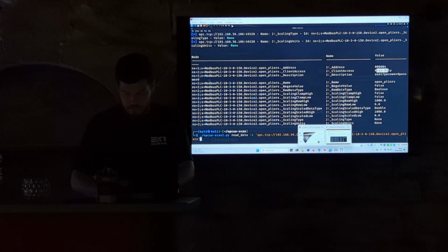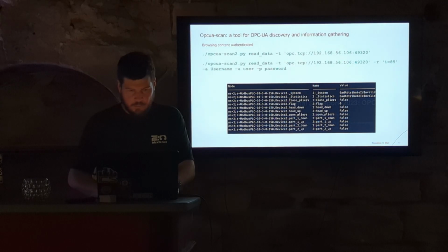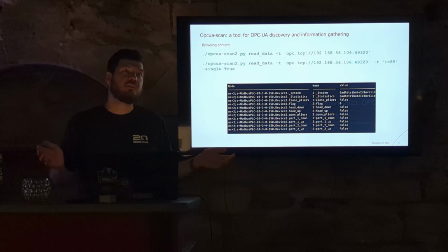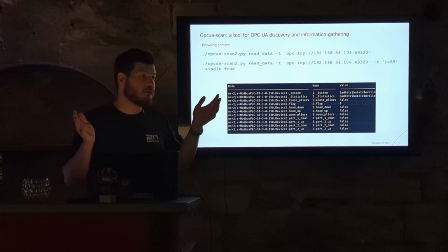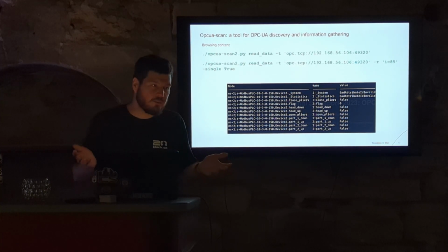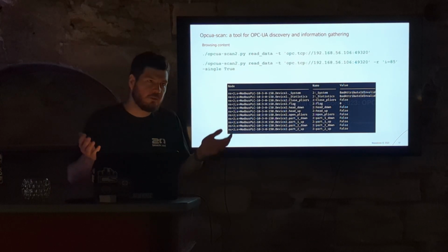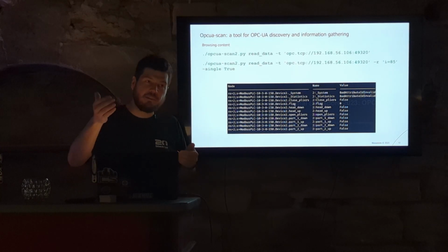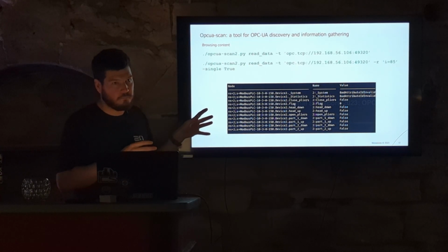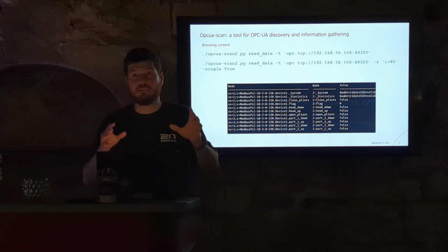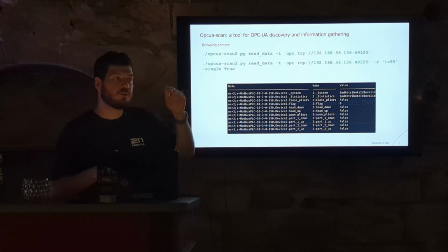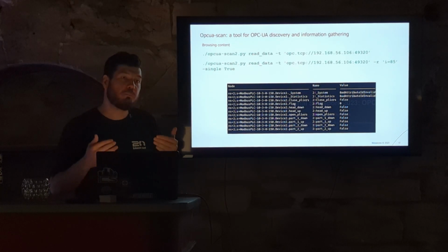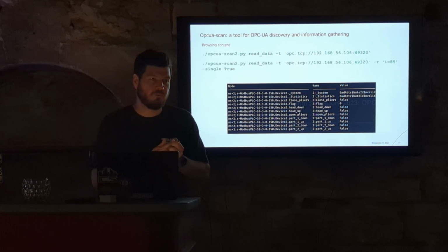Then let me go back here. It depends on what? Like it depends on the vendor or something like that. Like for example, each vendor is free to implement the standard the way it wants, and Kepware does it in a weird way because if I use the standard feature to get the access right, it's not the same as the real access right. And I think it's because OPC UA is still a moving protocol. There's a lot of different chapters in the specification, and I'm not sure authorization is fully published yet. So, you know, it's a bit weird.